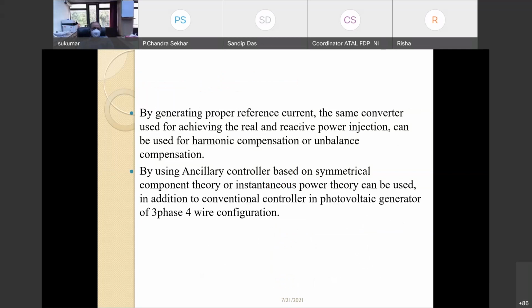Now, by generating proper reference current, the same converter used for achieving the real and reactive power injection can now be used for harmonic compensation and unbalanced current compensation as well. Besides, the ancillary control based on symmetrical component theory and instantaneous power theory can be used to go for a three-phase four-wire configuration and achieve the desired amount of power quality improvement due to the loads which are polluting the grid.